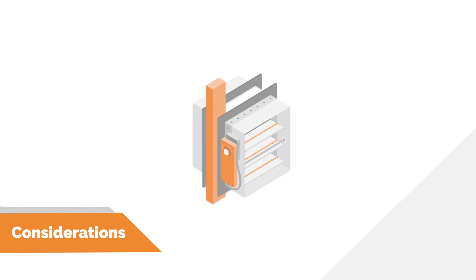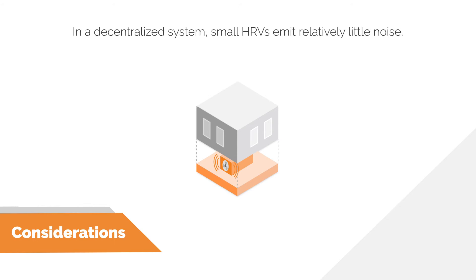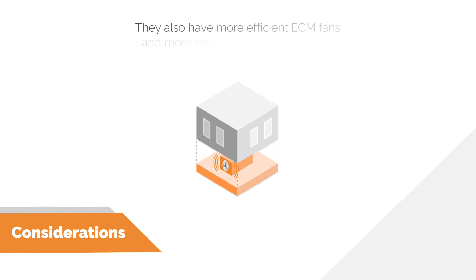Noise is always important but often overlooked in design. In a decentralized system, the small HRVs installed within the suite emit relatively low noise. Centralized or semi-centralized systems can be many times quieter and easily controlled as the HRV is not located within the suite. One benefit of high-efficiency HRV units used to reduce TEDI values is that they are typically much quieter than lower-efficiency HRVs. These high-efficiency HRVs have more efficient ECM fans, usually more insulation to dampen sound, and a more robust casing construction that helps further reduce breakout noise.